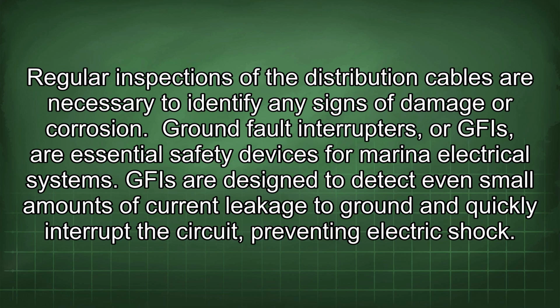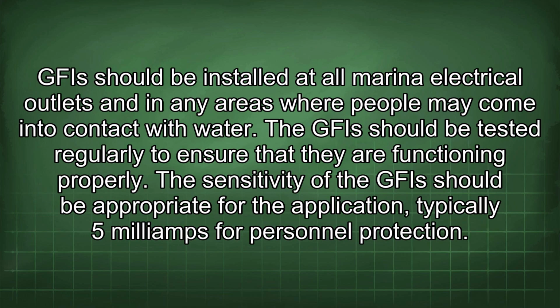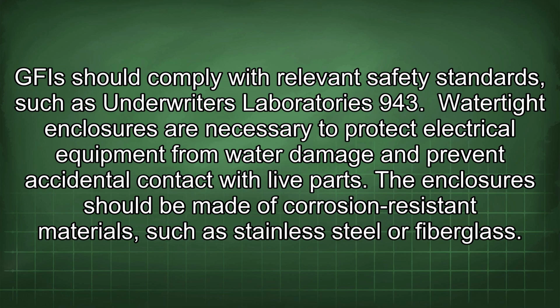Ground fault interrupters, or GFIs, are essential safety devices for marina electrical systems. GFIs are designed to detect even small amounts of current leakage to ground and quickly interrupt the circuit, preventing electric shock. GFIs should be installed at all marina electrical outlets and in any areas where people may come into contact with water. The GFIs should be tested regularly to ensure that they are functioning properly. The sensitivity of the GFI should be appropriate for the application, typically 5 mA for personnel protection. GFIs should comply with relevant safety standards such as Underwriters Laboratories 943.